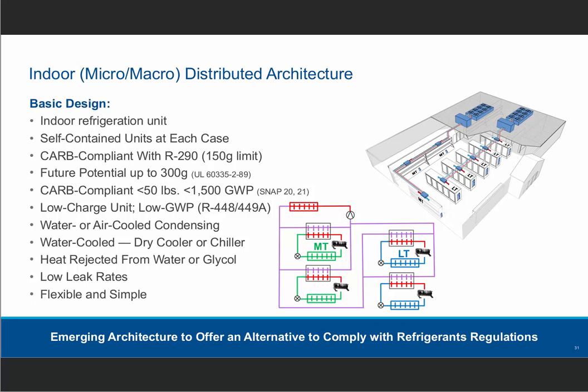Water-cooled is another option. The picture that I'm showing here on the screen is basically a store using the water-cooled version, where you see these small blue boxes representing the refrigeration unit. So in this case, sitting on top of display cases, and then the condensing side of those units being chilled by water that is coming through the piping from an external chiller. So basically the heat in those cases is rejected through the water or a mixture of glycol.